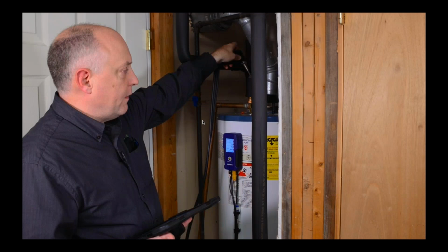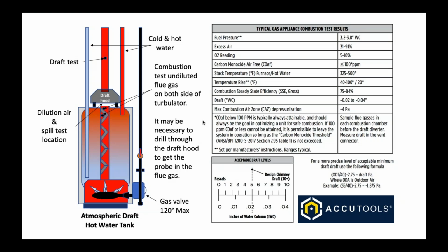Hot water tanks. I cannot stress enough, you should always be testing hot water tanks. In this case, this is my house. My hot water tank's not connected to my furnace because it's not common vented, but hot water tanks can be a significant source of CO. We're using a BluFlame analyzer here with an iPad. The app's really slick because it can start and stop the analyzer, so it makes it really easy for testing.